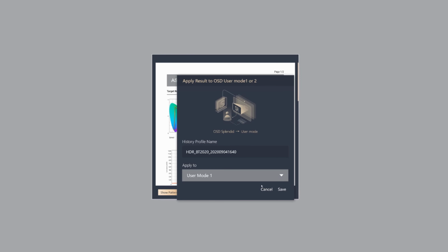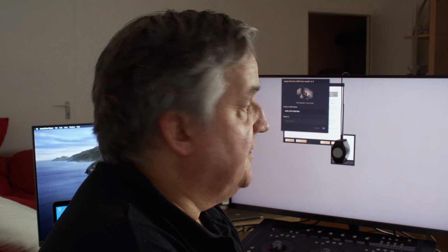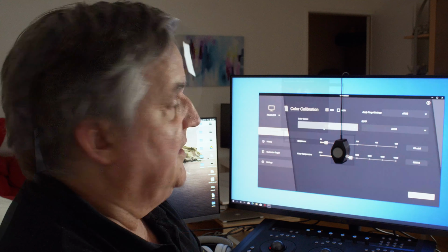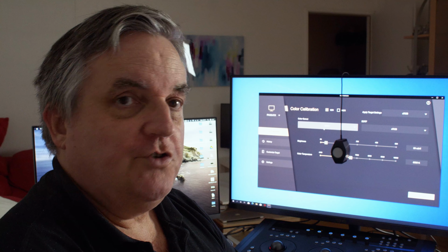And then we say put it into user mode 1, and there that happens now. And now it's stored into the user position number 1 inside the monitor. And the upside here is storing it inside the monitor. If you change computers, your calibration still remains. And having it on these presets inside is a fantastic way to do it. And inside the software, it actually will also give you a reminder when you need to recalibrate, because it is normal on occasion that after a while you should periodically calibrate your monitor.